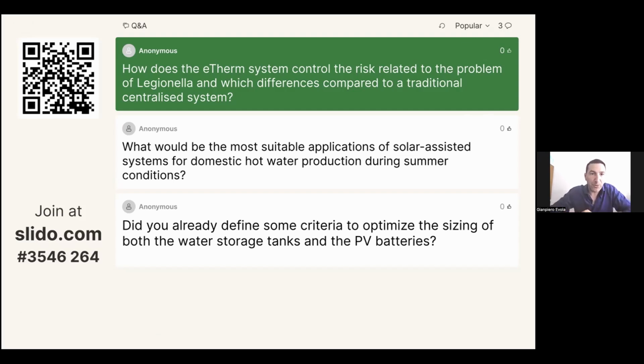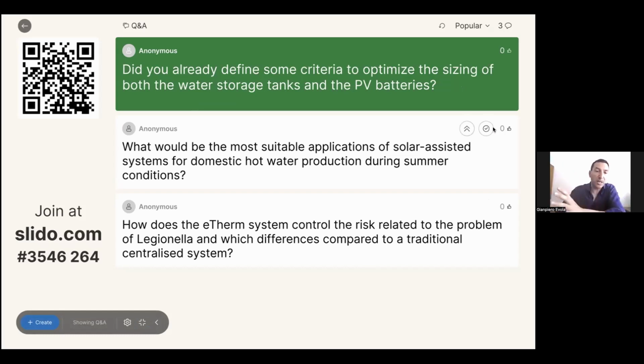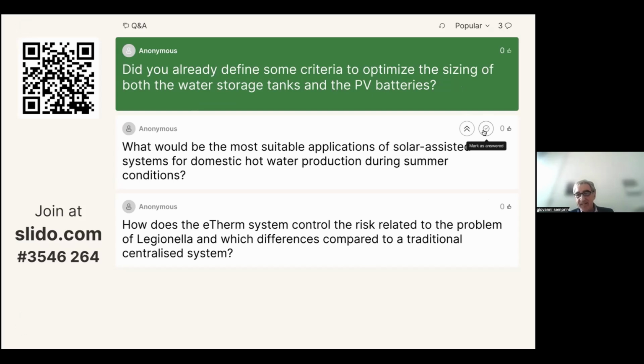Well, in this case, I remember, Giovanni, we have discussed it, and if I'm not wrong, we understood that the best thing is to have two heat pumps, one which works in cooling mode to manage space cooling, and the other one for domestic hot water. So two heat pumps and two separate storage tanks. Yes, I think it's very important to make the preliminary energy audit of the building before defining the final solution. Very important to evaluate the consumption, better evaluating the typical user profile, the hourly profile of the consumption, in order to optimize the solution.